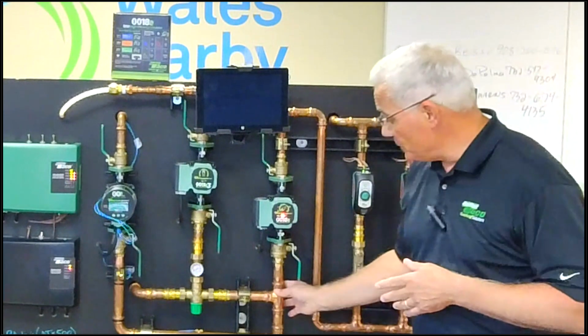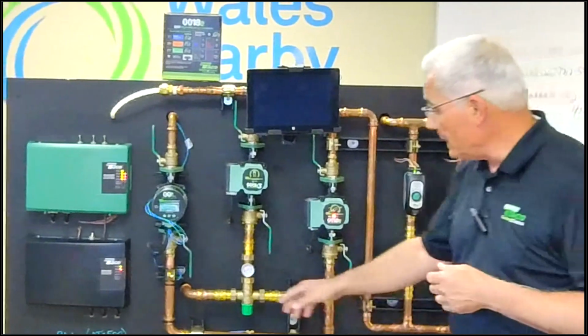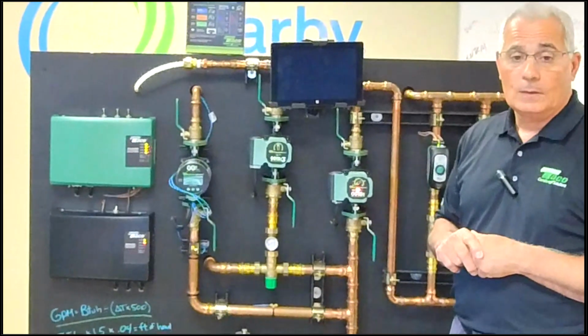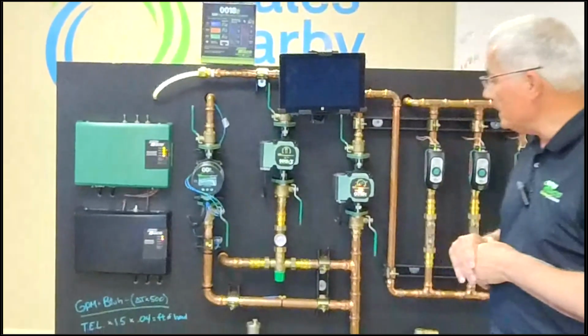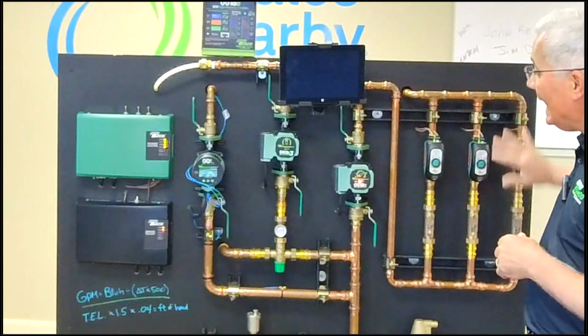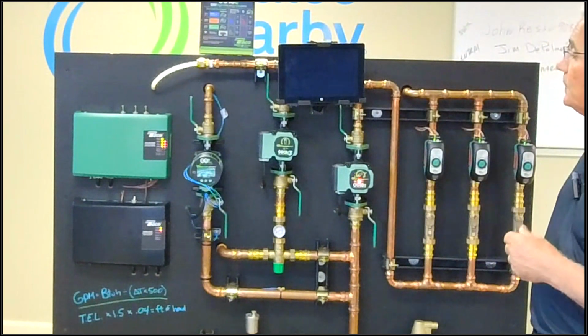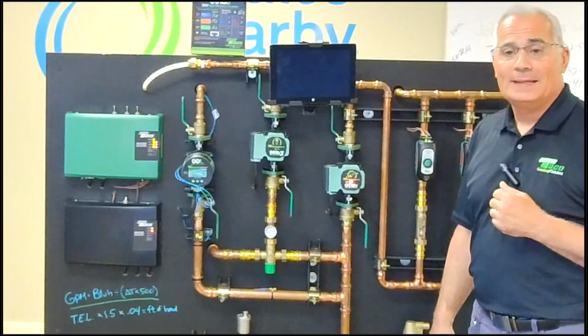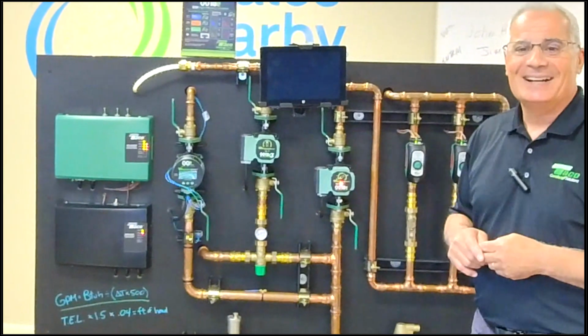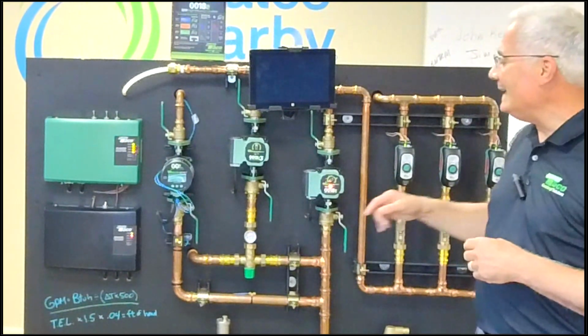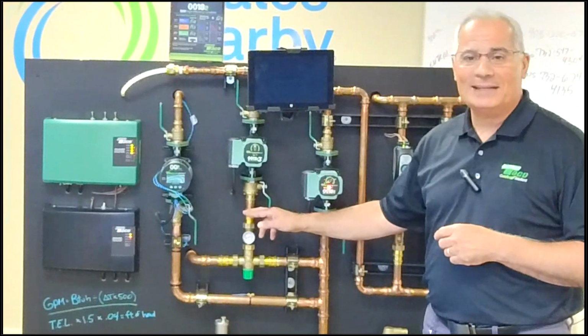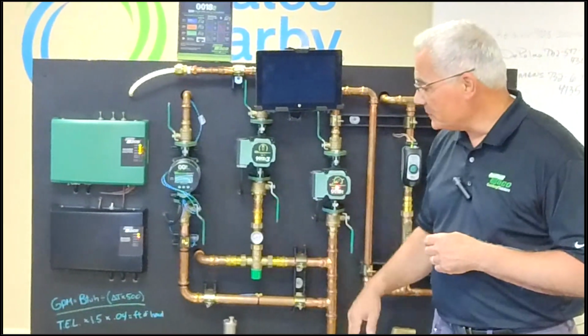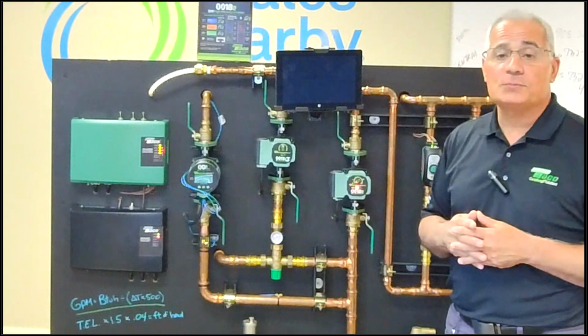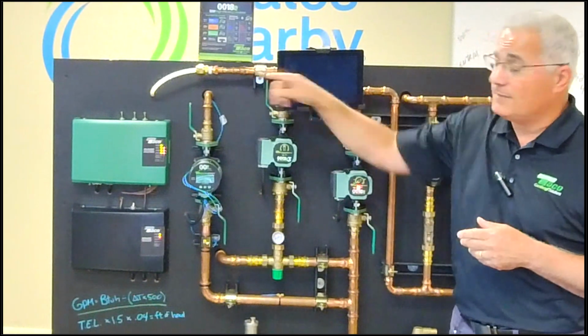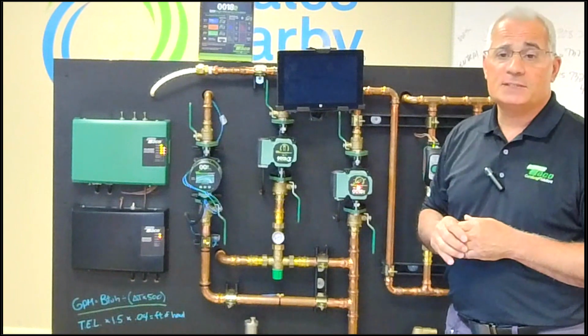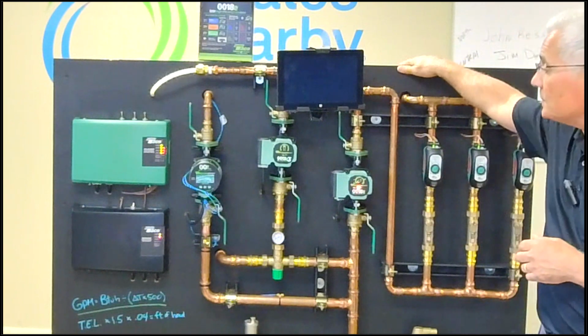As we move over here, you're going to see we have a T cut in, and we are now going to a mix valve. Taco makes the 5000 series mix valve. Since this would be a cast iron system, normally a 180 degree system, I need a lower temperature going out to my radiant system. So I have to put in a mix valve. Since this would typically be a very small radiant zone, we have about 75 feet of 5/16 tubing looped inside this display.